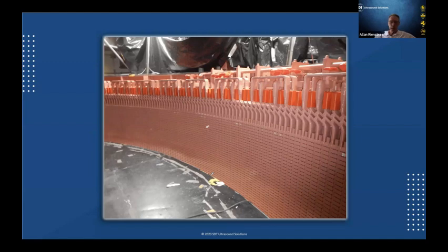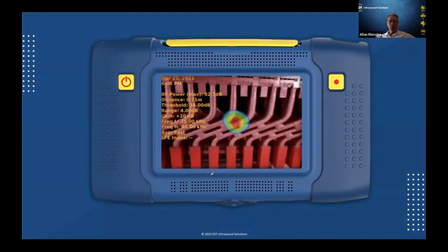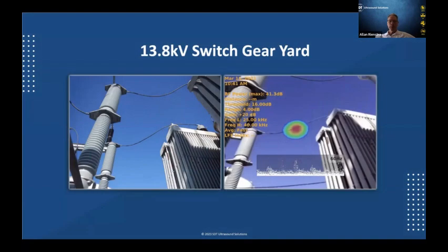They're running a super high voltage through this thing, and using his SonaView acoustic imaging camera, he isolated only one singular defect, and it was right there. He took a picture of it. He marked it off.